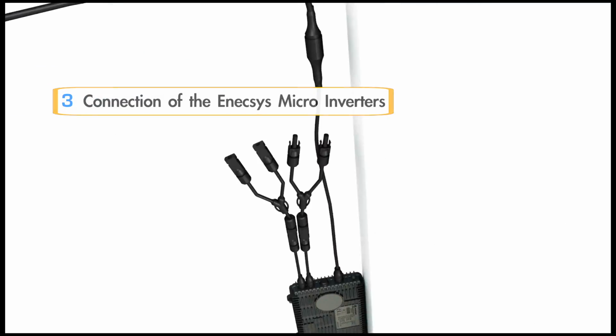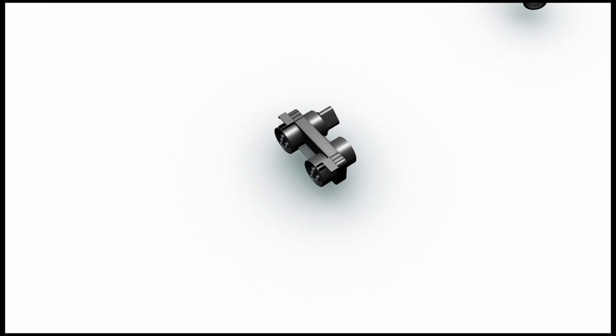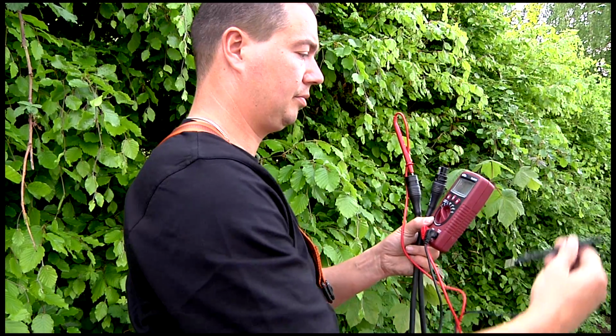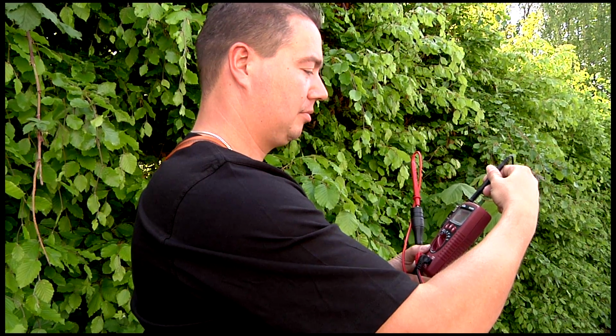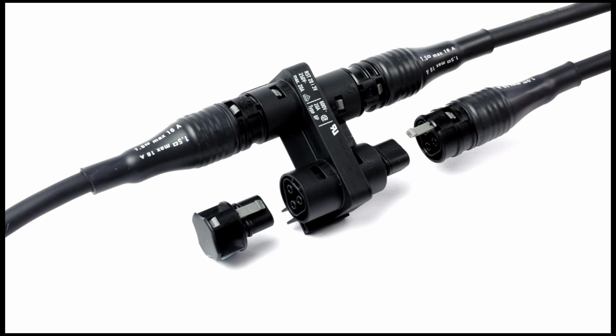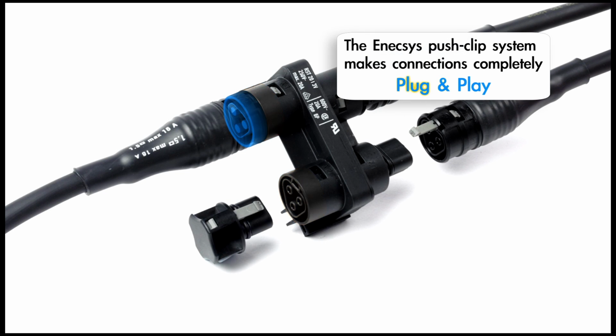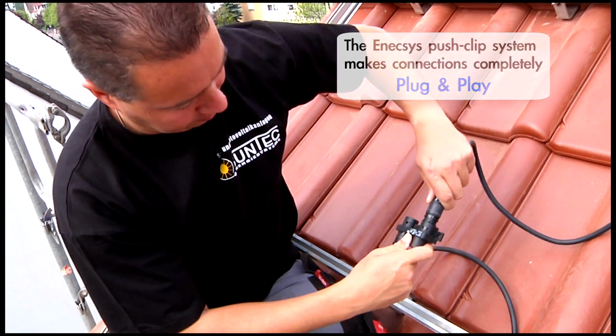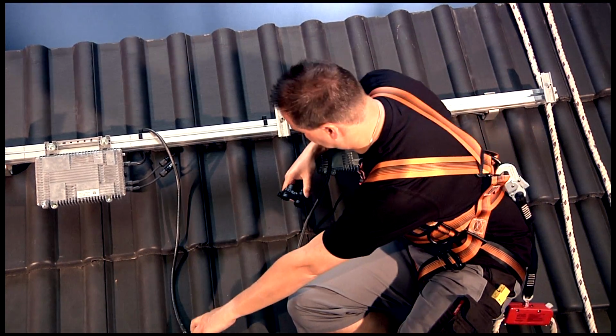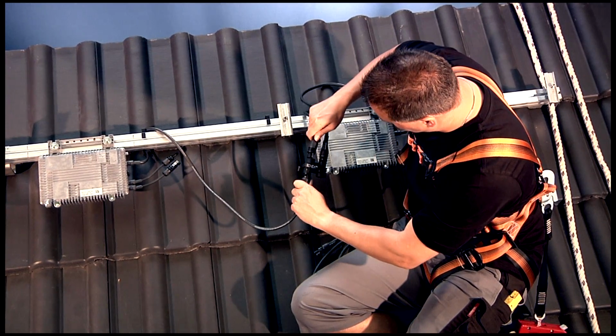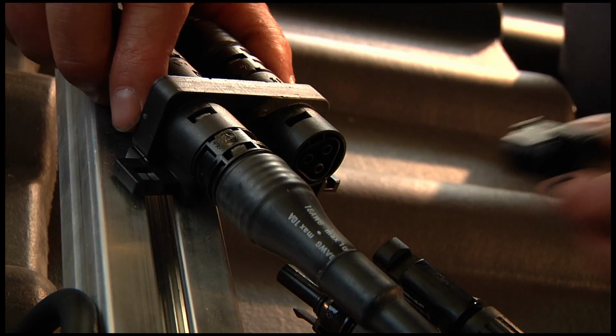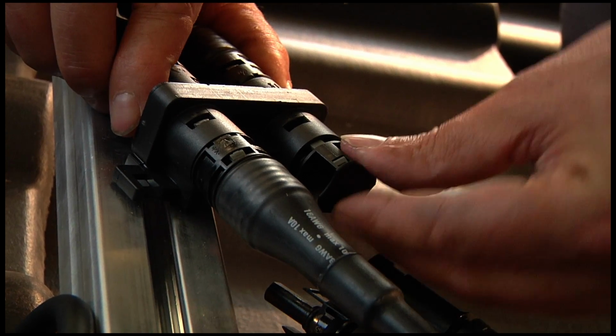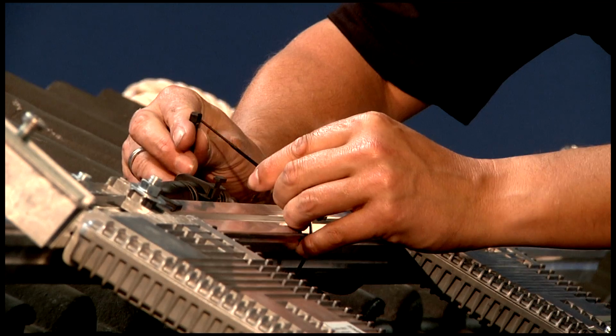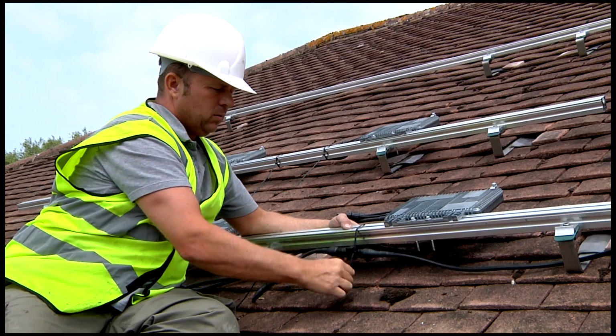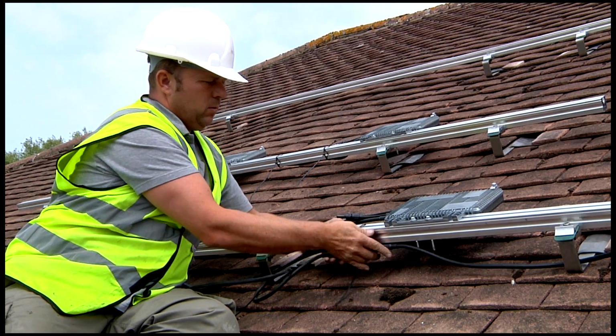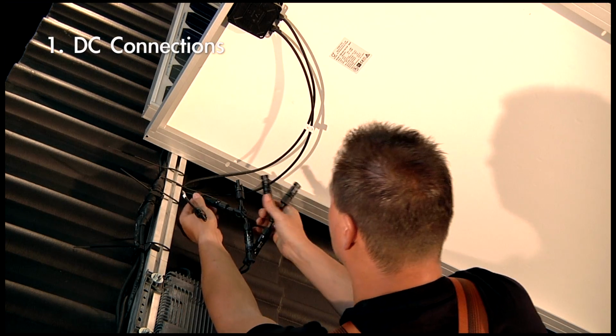Step 3, connection of the Enecsys microinverters. Before connecting the microinverters, it is advisable to test cables and distribution blocks to verify cable continuity and insulation resistance. The Enecsys push clip system makes the connections within the microinverter system completely plug and play. First, connect the Enecsys microinverters to distribution blocks using the provided AC extension cables. Next, attach end caps to any unused connections on distribution blocks and cables. Ensure the cabling is securely fastened to the railing system to avoid submersion in water. Finally, connect the solar PV modules to the Enecsys microinverters.